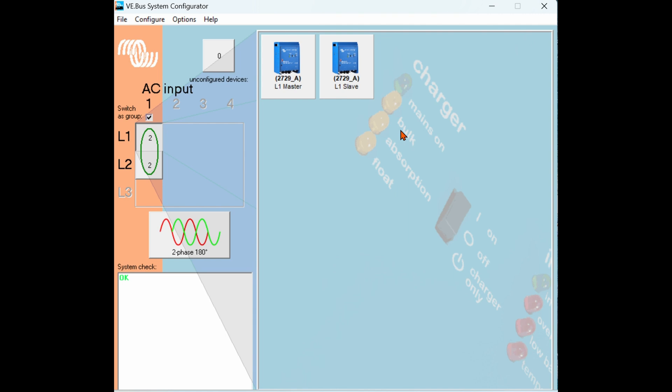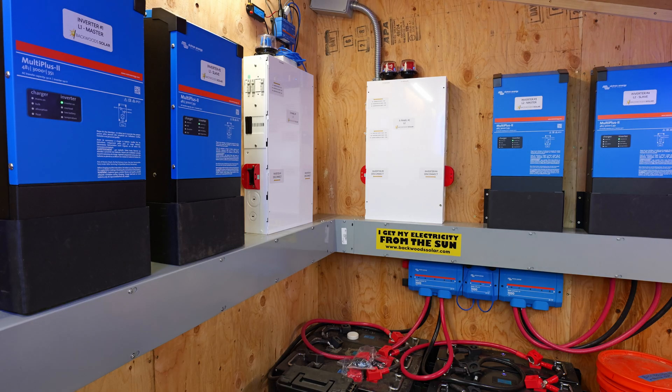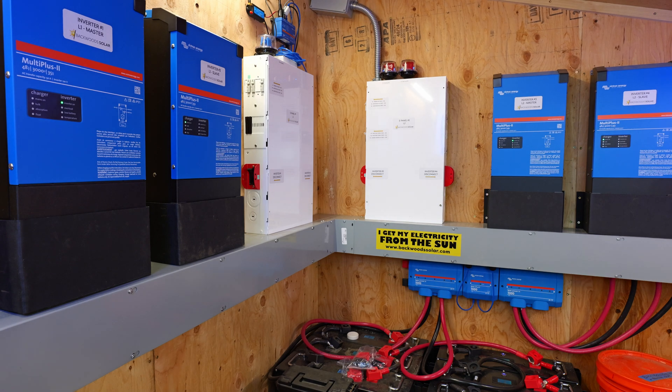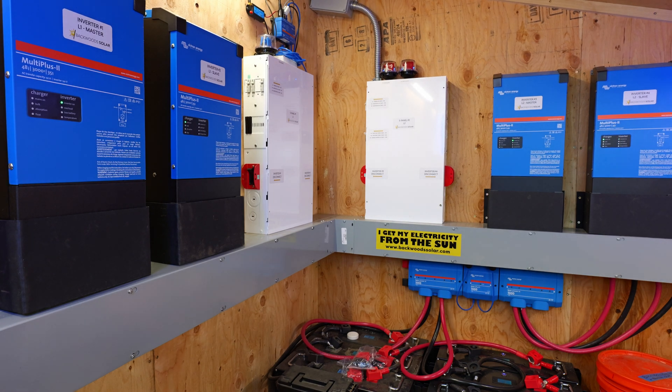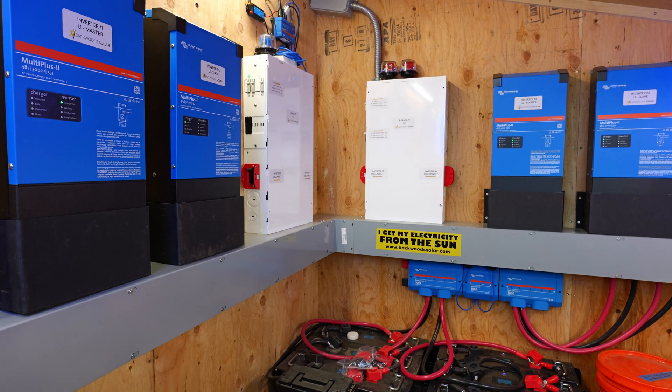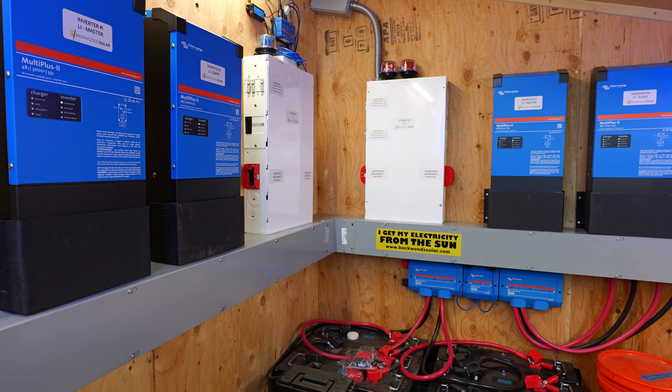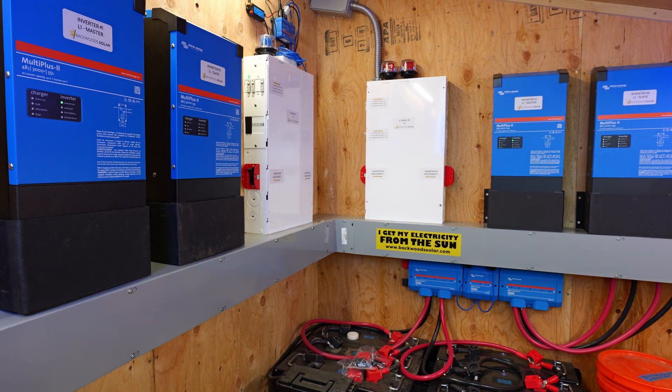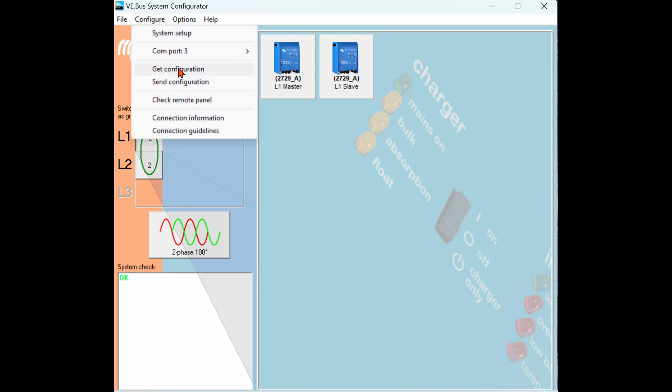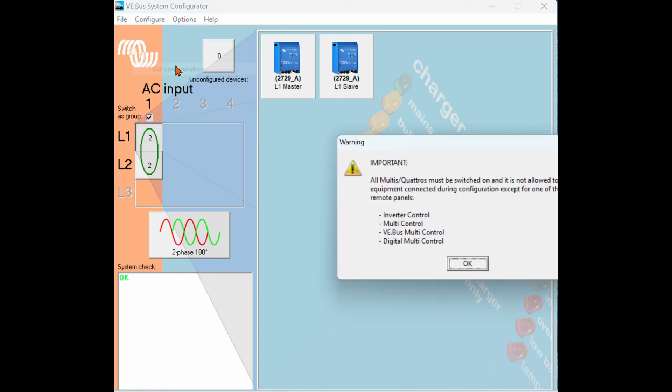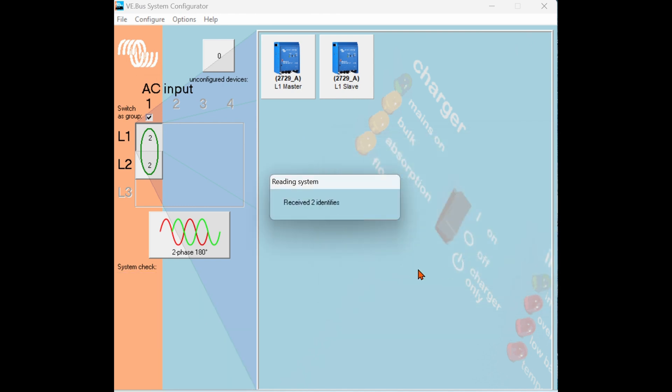Once the inverter configuration is sent you should see the inverters reset and have the master inverters with a solid green LED light and the slave or secondary inverters with a blinking green LED light. If you're dealing with an inverter system that's pre-programmed and you want to change the configuration of the system you can go up to configure and do get configuration. This will pull the file from an existing inverter system to allow you to modify it or make changes to it.